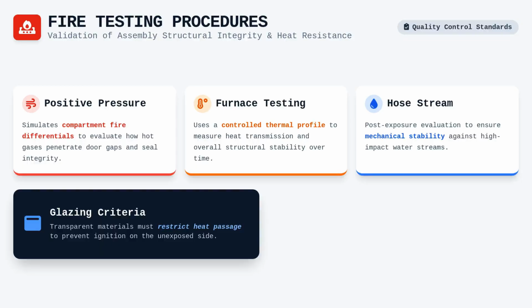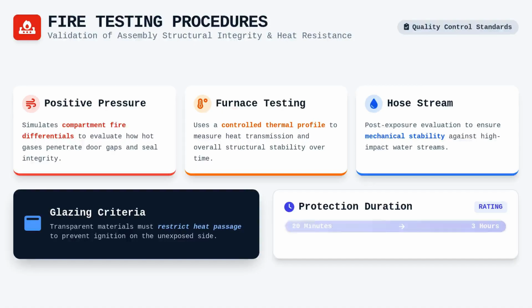For glazing materials, the thermal transmission criteria are equally stringent, as transparent materials must restrict the passage of heat to prevent ignition on the unexposed side. These standards ensure that doors provide a reliable duration of protection, typically ranging from 20 minutes to 3 hours depending on the fire resistance rating requirements of the partition.